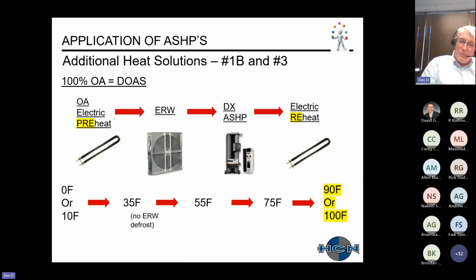That 35 is above our requirement, so there's no danger of that energy recovery wheel going to defrost mode. Then the leaving air temperature from our air source heat pump, and I've highlighted the 90 or 100 with our reheat. And once again, this is DOAS, so maybe you're providing just neutral air. Maybe you wouldn't need that reheat to be added, or maybe you want to put it in there for situations where your air source heat pump could go to defrost.